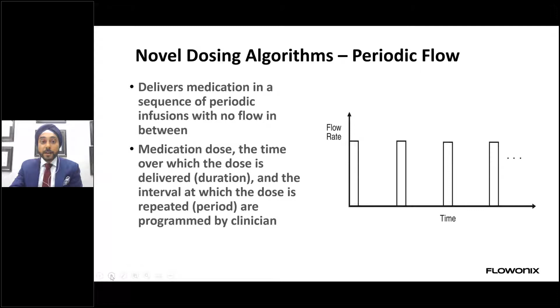This is a comparison now with the same type of pump, the Flowonix pump, again a valve-gated pump, showing the constant flow that we showed earlier in the lower part of the slide, but this time it's going to compare a periodic flow pattern. So again, 1 milligram per day is delivered by the pump, showing again no flow in between these 2 microliter boluses, comparing it to the lower part. In this unique flow pattern, the periodic flow was set to 6 sets of 8 microliter boluses and a total of 48 microliter boluses per day. So 1 minute every 4 hours, again, no flow in between each of the boluses.